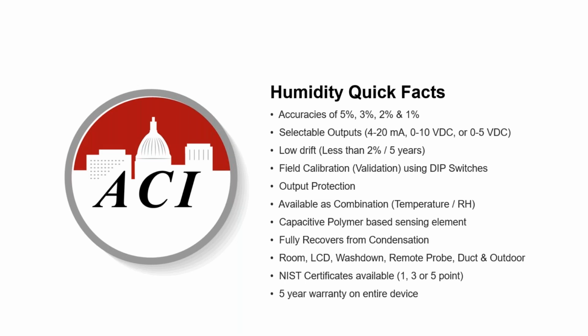So it's not just humidity. We can offer a temperature sensor in there, so you can have a temperature and CO or humidity sensor in the same enclosure. We have since added CO2 to this. I'll have to update that slide. We use a capacitive polymer-based sensing element. Some of our competitors use a resistive element, and the difference there is a capacitor element, if you get it completely saturated or 100% RH, which sometimes spaces can get to that, it actually comes back to life. A resistive type sensor will not. It'll fail in the field if it gets higher than about 90% humidity. So that's the reason that we use a capacitive based sensing element.